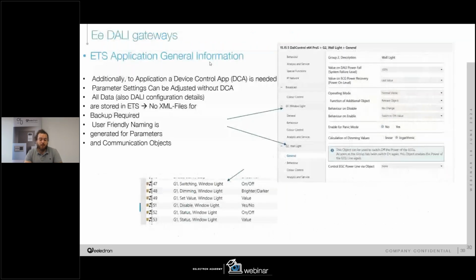One very important thing that we had as an update in our portfolio with these gateways is that now every gateway that we have in portfolio is compatible with a new DCA. It is a device control app that you can find directly in the MyKNX store, or now you can also download it directly from our website. Very easily you have to add this ETS app in your ETS, and later you will be able to control every parameter of the DALI gateway. And another thing that I want to tell you now, all the information is inside the ETS project, so you don't need any external export or external software to save the configuration. We put every knowledge that we have in our ETS on how we made the ETS also in the DALI gateway, like the friendly naming and the opportunity to change naming of ECG groups and so on.